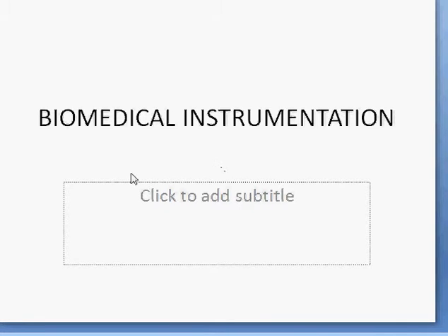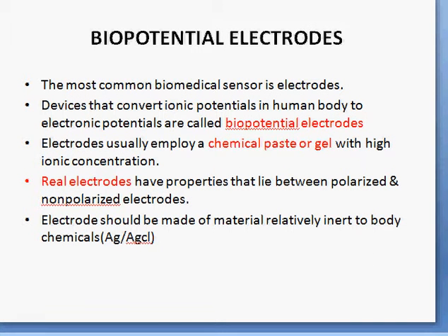Hello, I am going to take a small topic from biomedical instrumentation which is biopotential electrodes. The most common biomedical sensor is electrodes. Devices that convert ionic potentials in the human body to electronic potentials are called biopotential electrodes. Electrodes usually employ chemical paste or gel to increase the ionic concentration.